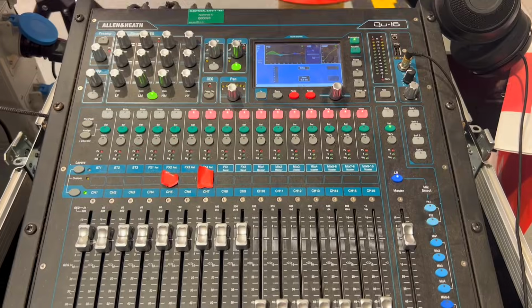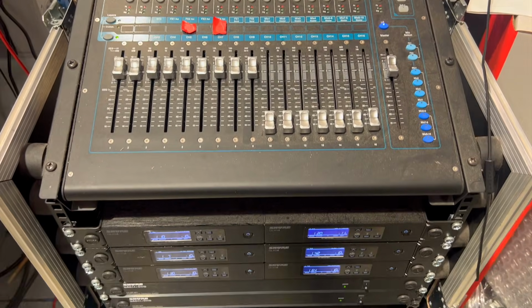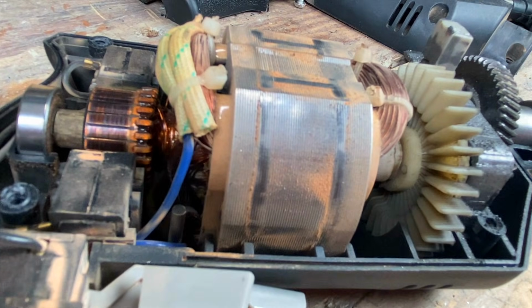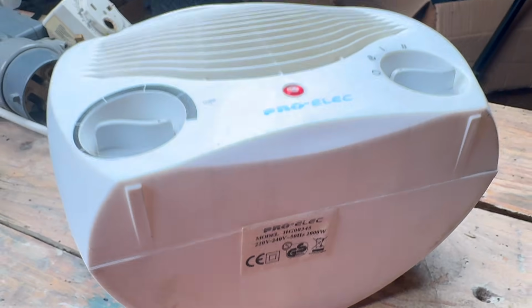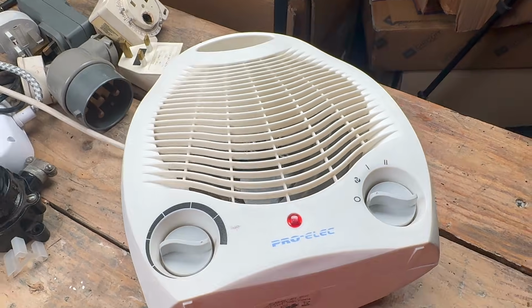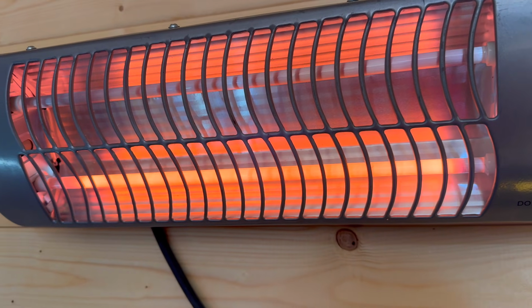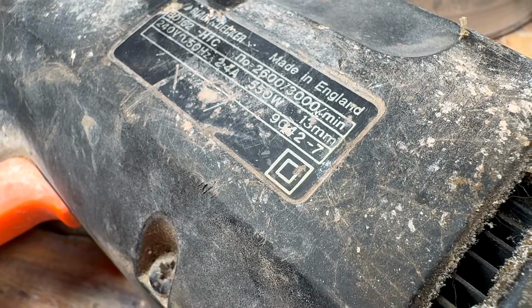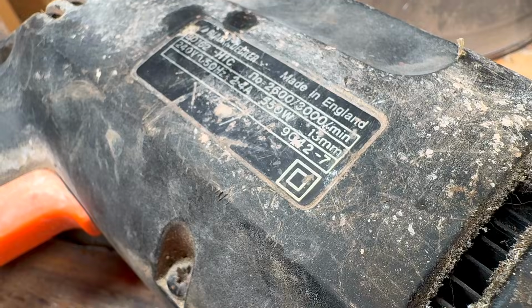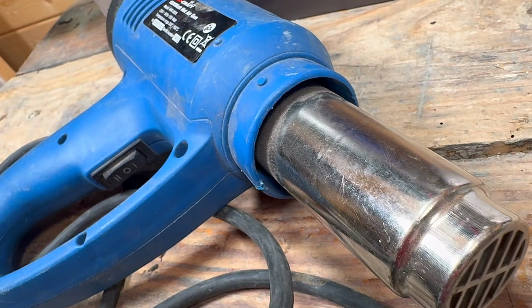But not all Class 2 equipment looks like plastic. Metal case media players, metal desk lamps, many power tools, luminaires, and some convector heaters may use double or reinforced insulation internally even when metalwork is exposed externally. Class 2 equipment is identified by the double square symbol. The inner square represents basic insulation and the outer square represents supplementary insulation. Class 2 is all about the insulation doing the work. No earth, no reliance on the installation.